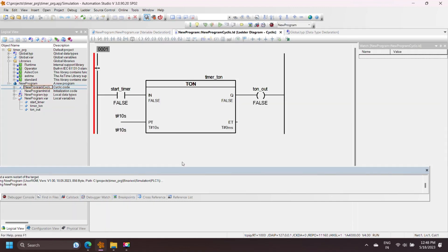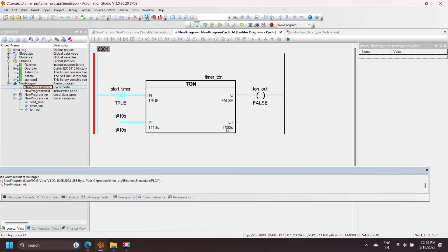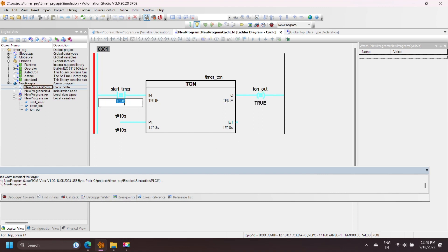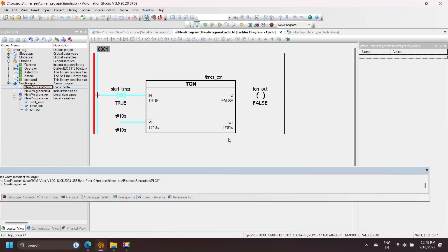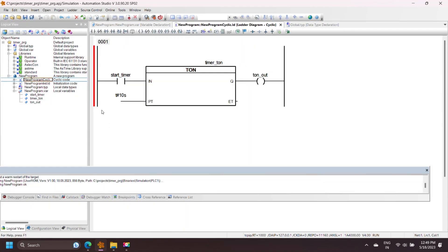On-delay timer instructions delay the output after the timer input signal has changed from false to true. The output is set to true after the preset time has elapsed. If the timer input is set to true, timer operation starts and increments the elapsed time (ET). When elapsed time equals preset time, the timer output Q is set to true. The base for incrementing elapsed time is 10ms.